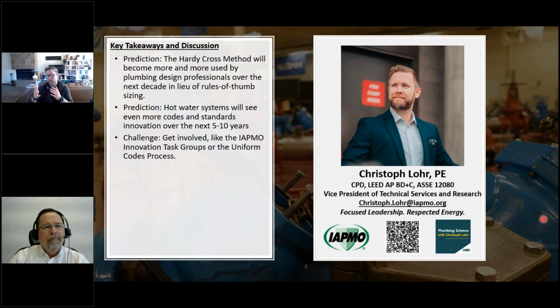to demonstrate the difference in approach. Now, if you need to adjust the flow rate in one of those branches and you have a cartridge type automatic balancing valve, you may be a little bit stuck. You might have to swap out the whole system. An adjustable, automatic balancing valve may be a good fit, but sometimes your control range for the automatic types, again, depending on manufacturer, may not be as good as for a cartridge type. So this is the really deep dive into understanding how this device, which is needed, impacts the whole system. So does that answer the question, Kevin?